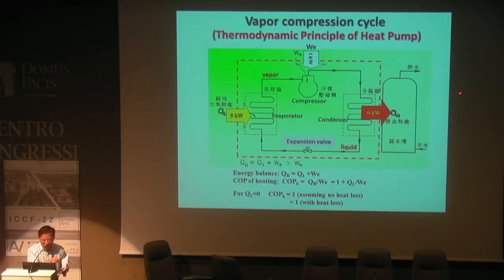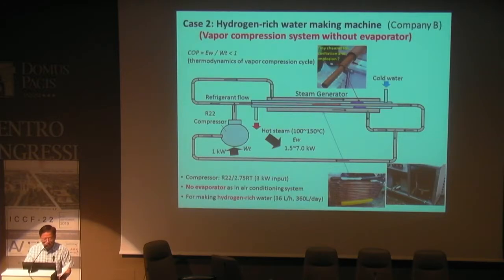And with today's technology, with 1 kilowatt input to the compressor, you can absorb about 5 kilowatt of heat here. Then in total, you get 6 kilowatt output. So the energy balance tells you output is equal to the sum of the input of these two. And for heating, the COP is this. If the evaporator does not exist, or is 0 for heat transfer, then COP for heating should be less than 1 if there's a heat loss. But a strange thing happens in this machine.